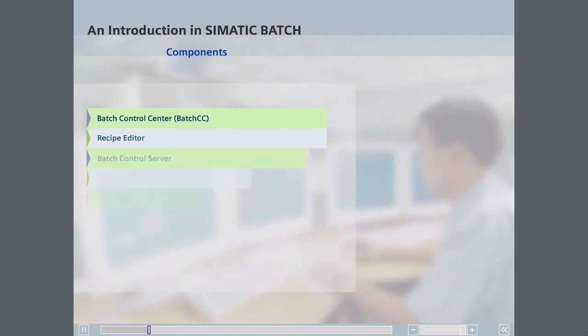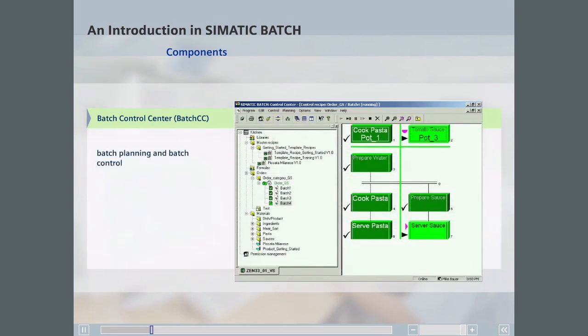The Batch Control Center is the central component in Simatic Batch for batch planning and batch control. It is used to read in the process cell data of the basic control, specify user rights for all Simatic Batch functions, define the input materials used and the end products and by-products produced in the process, and create and maintain master recipes and libraries.